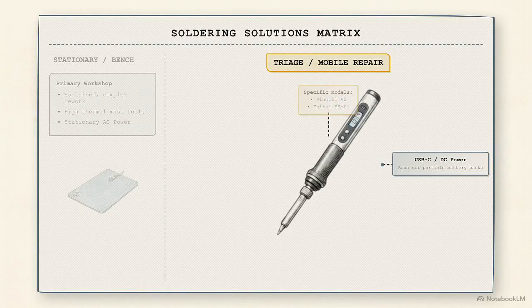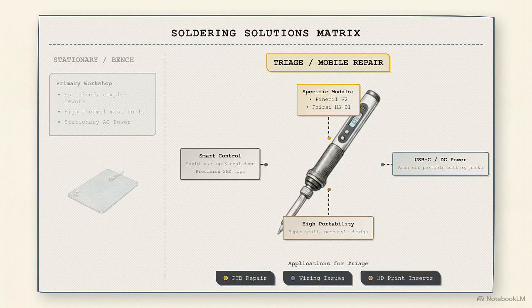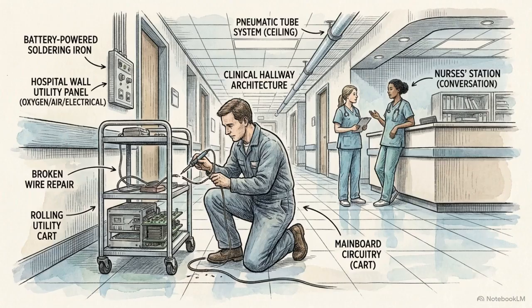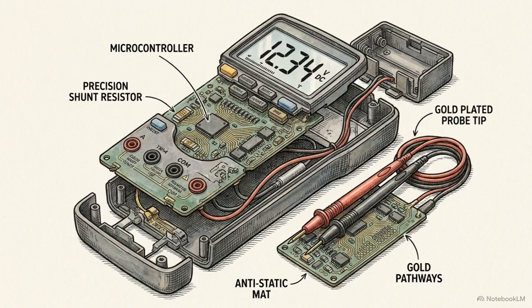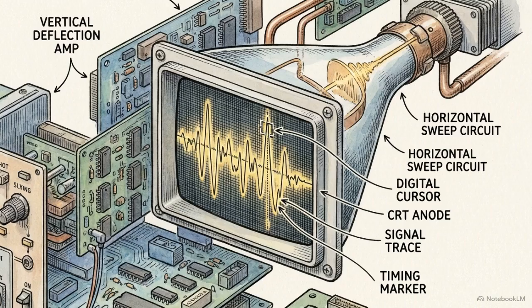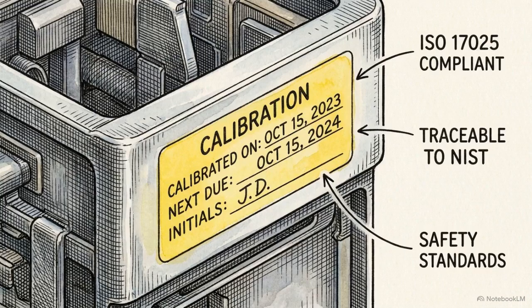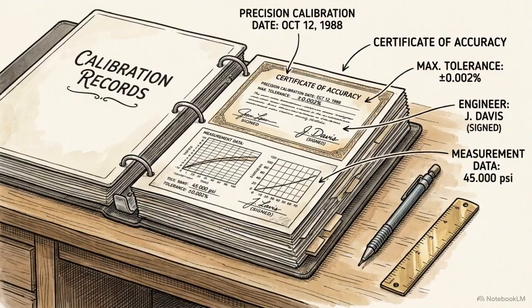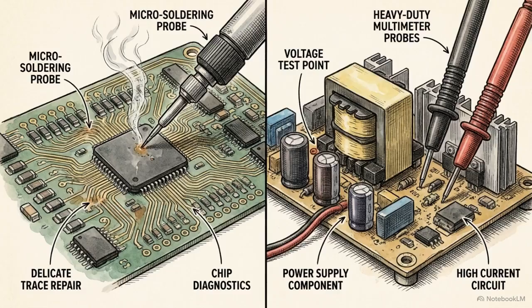For triage, USB-C-powered smart soldering irons like the Pinecil V2 or Fnirsi HS-01 offer high portability for quick mobile fixes. While smart irons enable rapid wire repairs on the hospital floor, they lack the sustained heat and dual-channel capability needed for prolonged desktop rework. Beyond soldering, your baseline diagnostics revolve around digital multimeters to check voltage and oscilloscopes to visualize waveforms and detect timing issues. These diagnostic tools must be NIST traceable. This requires a commitment to recurring administrative recalibration schedules, so every measurement taken in the shop remains legally defensible. The objective at the bench level is precisely matching the thermal and diagnostic capabilities of your tools to the specific legal liability of the repair.